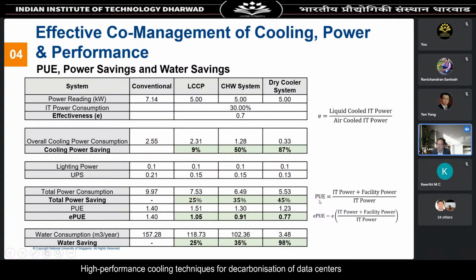Precisely because of the definition of PUE: it's defined as IT power plus facility power, divided by IT power. For liquid cooling, because IT power reduces by, say, 30%, you actually get penalized, since if IT power is reduced by 30% in both numerator and denominator, your PUE will actually increase. But this is not to be frowned upon, in fact it should be celebrated, because besides the reduction in facility power, if you're also able to drop your IT power significantly, that's very advantageous.